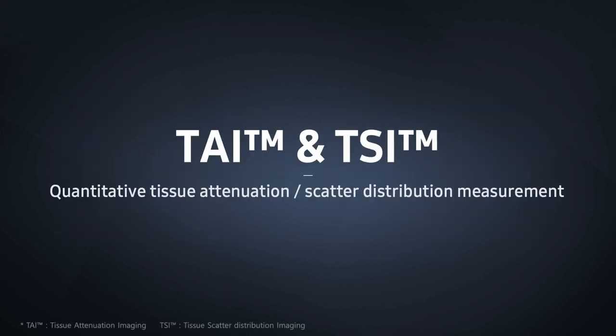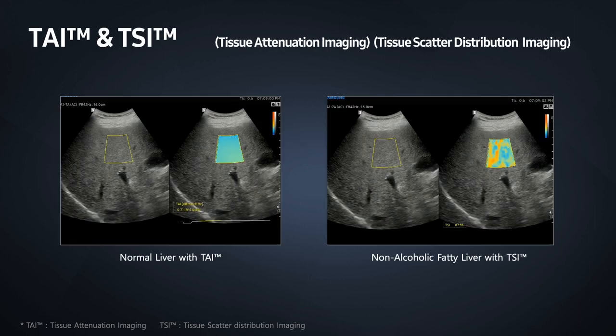TAI and TSI: Ultrasound energy is subject to attenuation as it propagates through tissue. The amount of attenuation experienced is dependent upon the media it travels through. In addition to attenuation, the propagation of sound through liver also generates a multitude of small diffuse scattered reflections. It is these small scattered reflections that comprise the liver parenchymal image. Tissue attenuation imaging (TAI) provides a quantitative measurement of attenuation as sound travels through liver parenchyma.